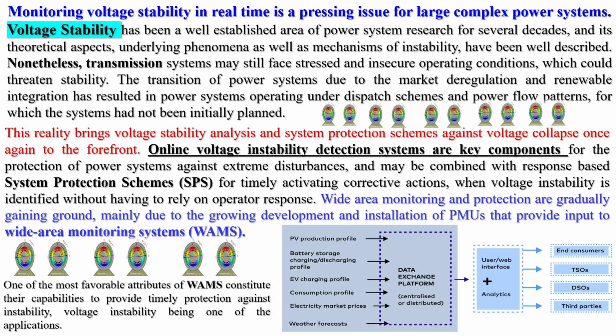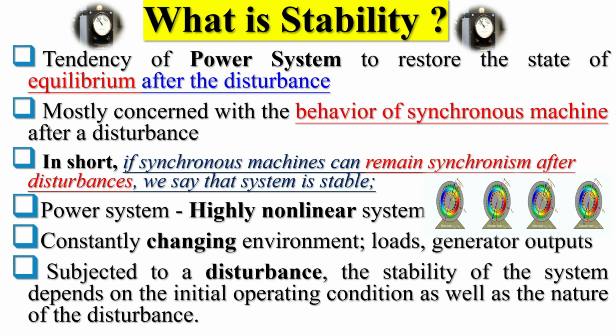Online voltage instability detection systems are key components for the protection of power systems against extreme disturbances, and may be combined with response-based system protection schemes, SPS, for timely activating corrective actions when voltage instability is identified, without having to rely on operator response. Wide area monitoring and protection are gradually gaining ground, mainly due to the growing development and installation of PMUs that provide input to wide area monitoring systems, WAMS. One of the most favorable attributes of WAMS is their capability to provide timely protection against instability, voltage instability being one of the applications. Let us discuss what stability actually is.